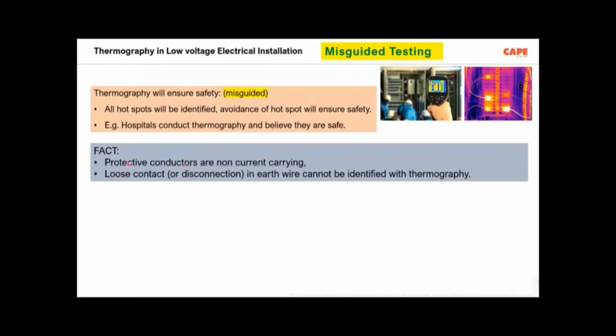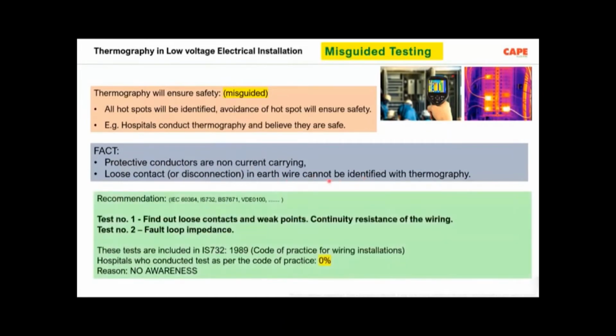So the fact is, protective conductors are non-current carrying. Loose contacts in an earth wire cannot be identified with thermography. And if you really want to find out loose contacts, you should do the test called the continuity resistance of the wiring, which is test number 1 in the sequence of 10 tests recommended in IS732. The second test which I would recommend is the fault loop impedance test, which is the 6th test in the sequence of the IS732.